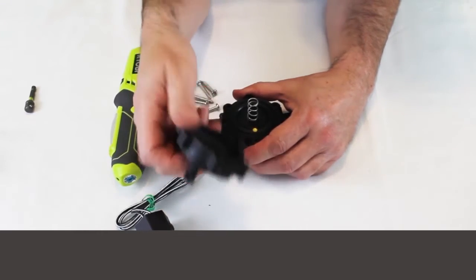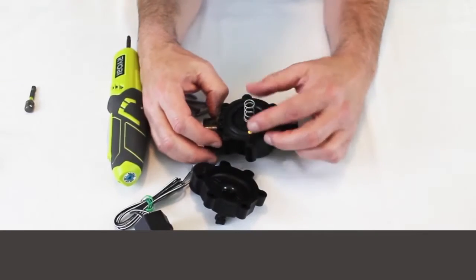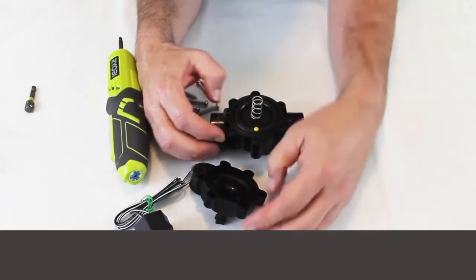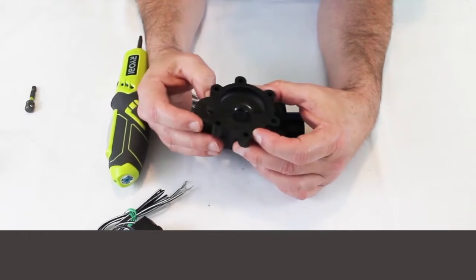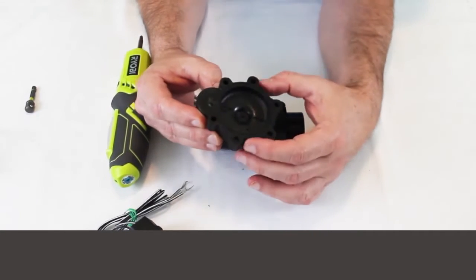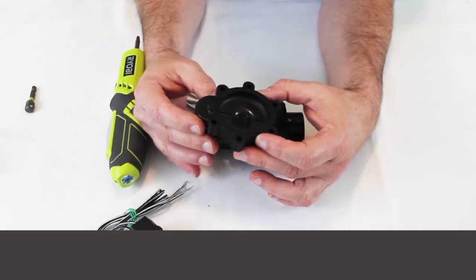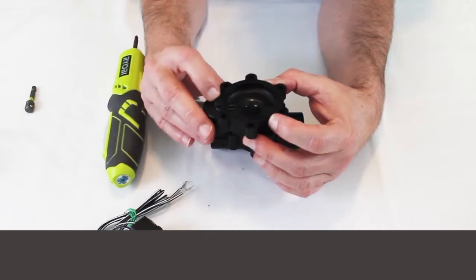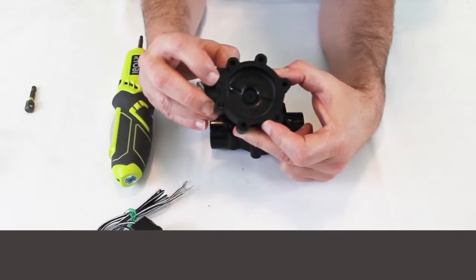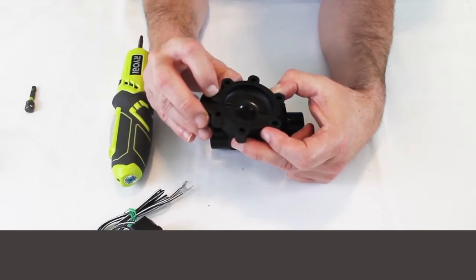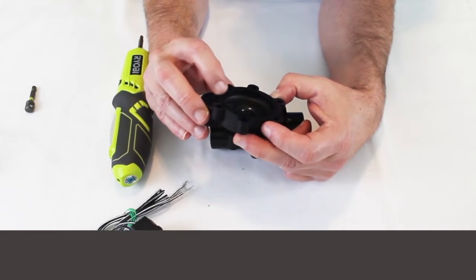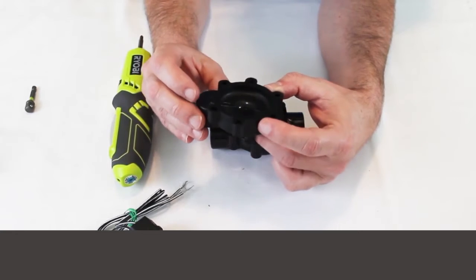Alright, take this one apart here. And as we look here, the top, the bonnet piece here is a really simple construction. If you're just rebuilding it and just putting the original parts back on, just inspect the little pilot hole here for the solenoid, which is very, very small on this one. Just inspect it, make sure that there's nothing down in there.